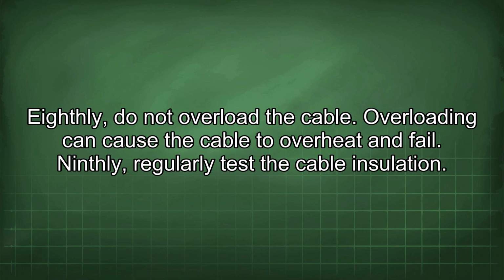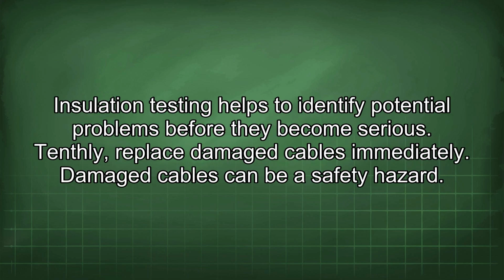Ninthly, regularly test the cable insulation. Insulation testing helps to identify potential problems before they become serious. Tenthly, replace damaged cables immediately. Damaged cables can be a safety hazard.